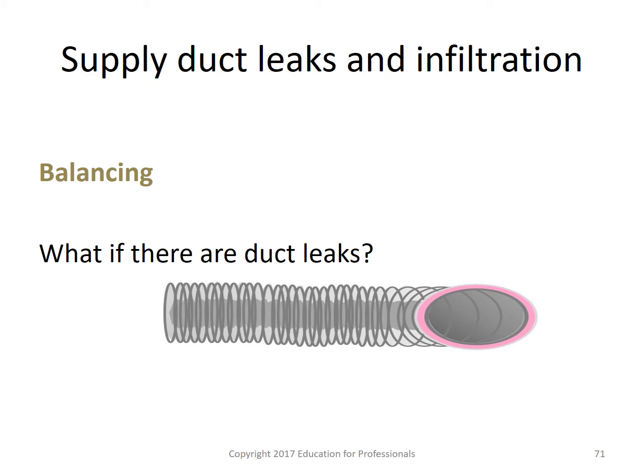In general, forced air heating and cooling systems should be balanced. It's almost an imperative. The amount of air delivered through the supply ducts should be equal to that drawn through the return ducts. And if the two volumes are unequal, pressure imbalances may occur in the home, resulting in increased air leakage and possible health and safety problems.